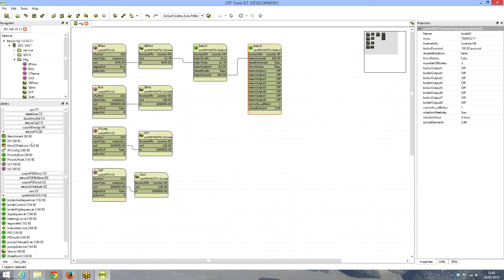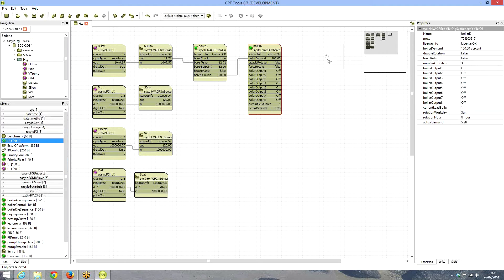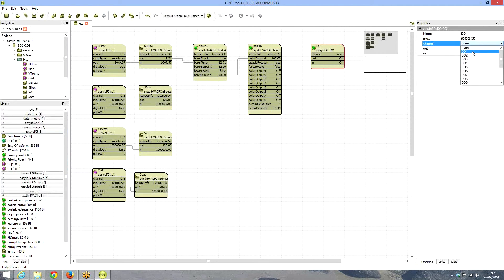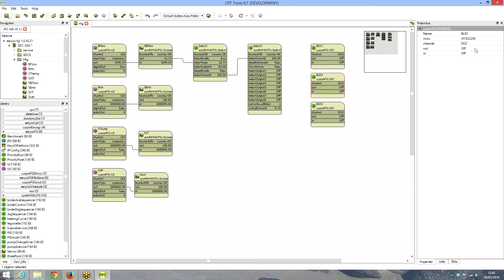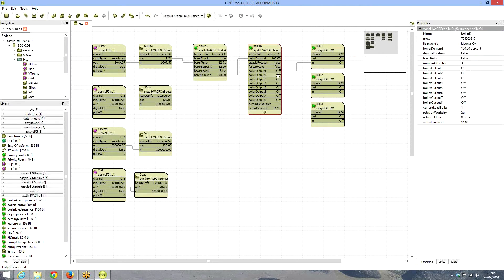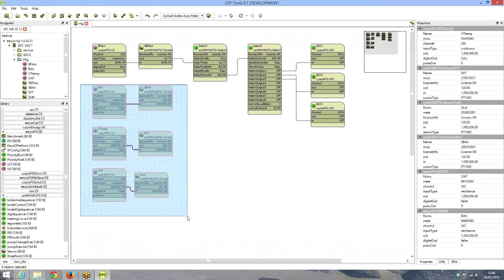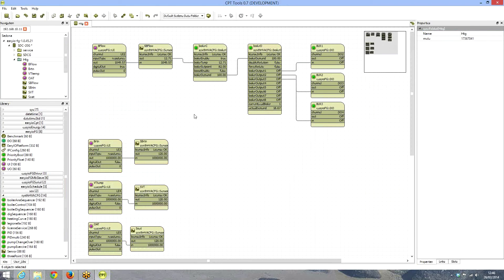We go to the FG kit for the controller and take the digital output objects. Boiler one is connected to channel one, boiler two to channel two, and so on. We use copy-paste for all three boilers, changing the physical channel number where each boiler is wired, then link the outputs from the sequencer to each digital output object.